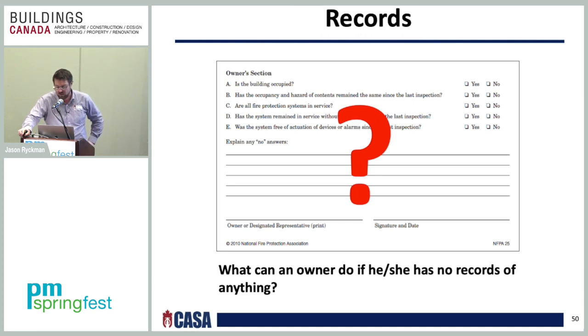Therefore, if the owner has no records, then they must be replaced or recreated. A complete inspection, testing, and maintenance program will have to be performed in order to establish baseline records for comparison. If the owner has none of the original records, basically they have to reproduce them, okay? And to do that, you have to basically get an engineer to recreate everything. So it becomes very cumbersome, and ultimately you have to have those records in place.